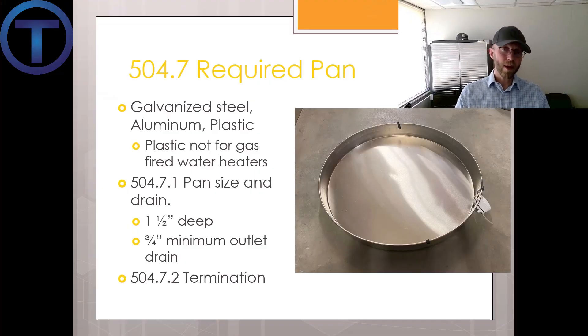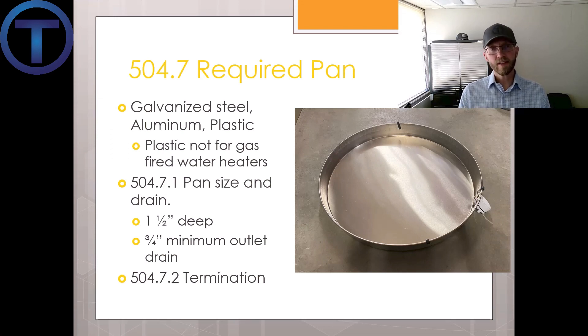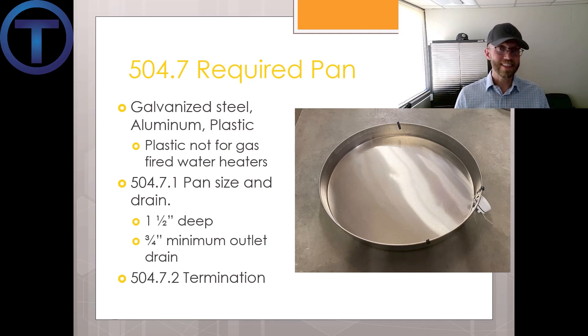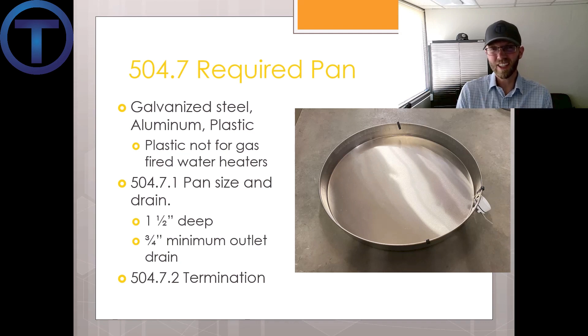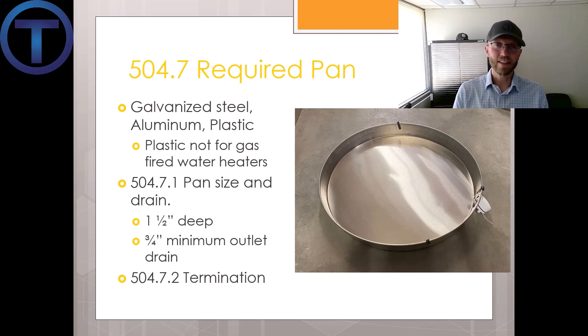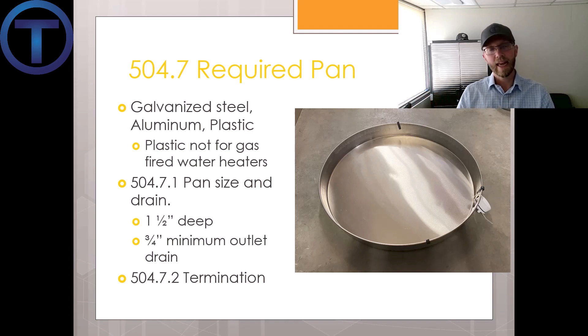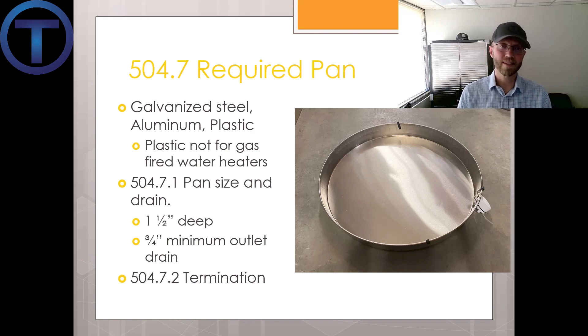504.7 tells us about when we need a water heater pan. We need a pan when a leak from the water heater would cause damage to the structure. In a wood-framed building with wood subfloors and joists, if water gets out it will rot the subfloor, damage the joists, and affect the structure holding the tank — the water heater could fall through the floor.